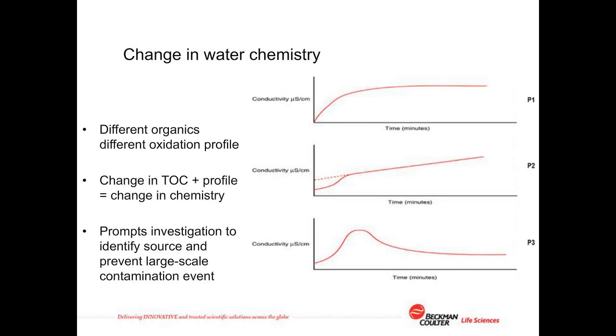Monitoring the TOC level itself may give us sufficient information, but one other indicator that things may be going wrong is a change to the type of organic contaminant present in the water. TOC analyzers that can report a change in the oxidation profile of the organic in the water may actually help us spot when things are starting to go wrong in time for us to take action before an excursion appears. An elevation in TOC levels combined with a change in the oxidation profile of the organic may well hint that not only are the TOC levels creeping up, but the type of organic getting into the water system has changed as well, leading us to carry out more in-depth water grab sample analysis to check what might be going wrong.